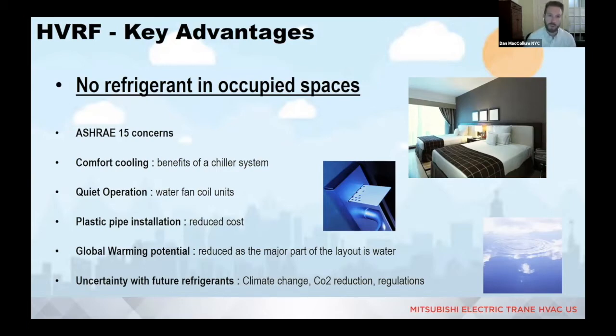So your whisper quiet VRF system becomes more of a soft whisper quiet system with HVRF. And for those of you like me who are concerned about the global warming impact of these type of systems, even though there is refrigerant still inside the system, it is substantially less than a traditional VRF system. And there are so fewer brazed connections, which can ultimately be failure points in the system. The likelihood of a leak is drastically reduced as well.